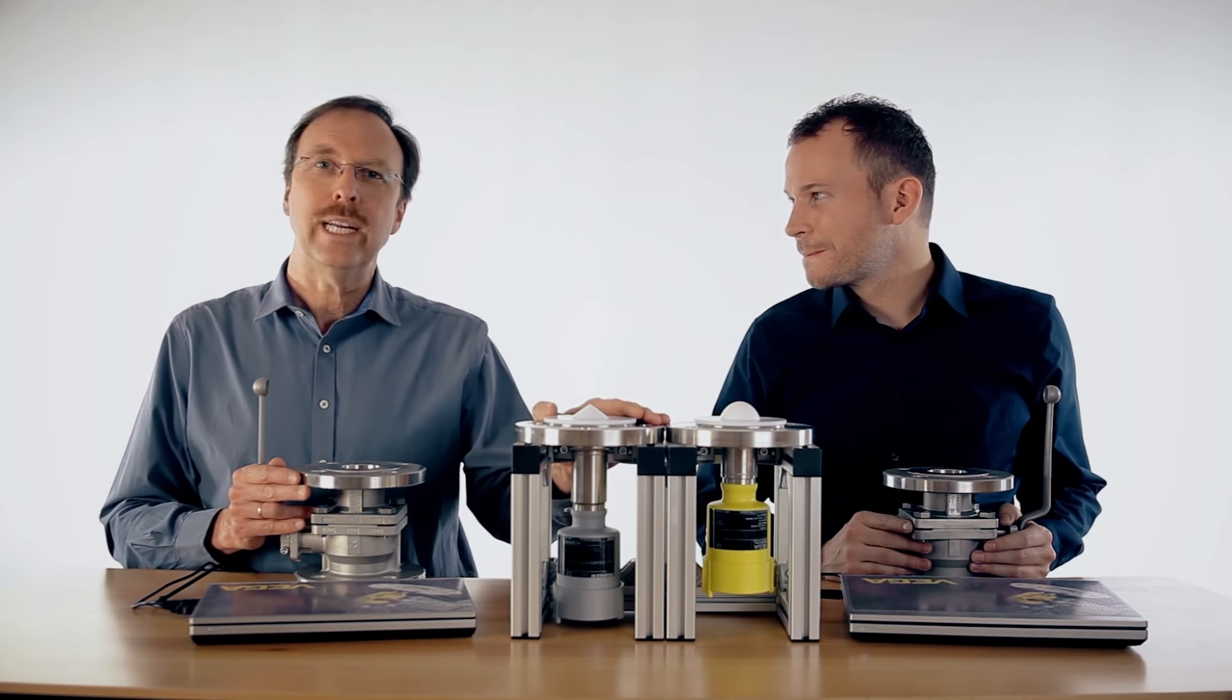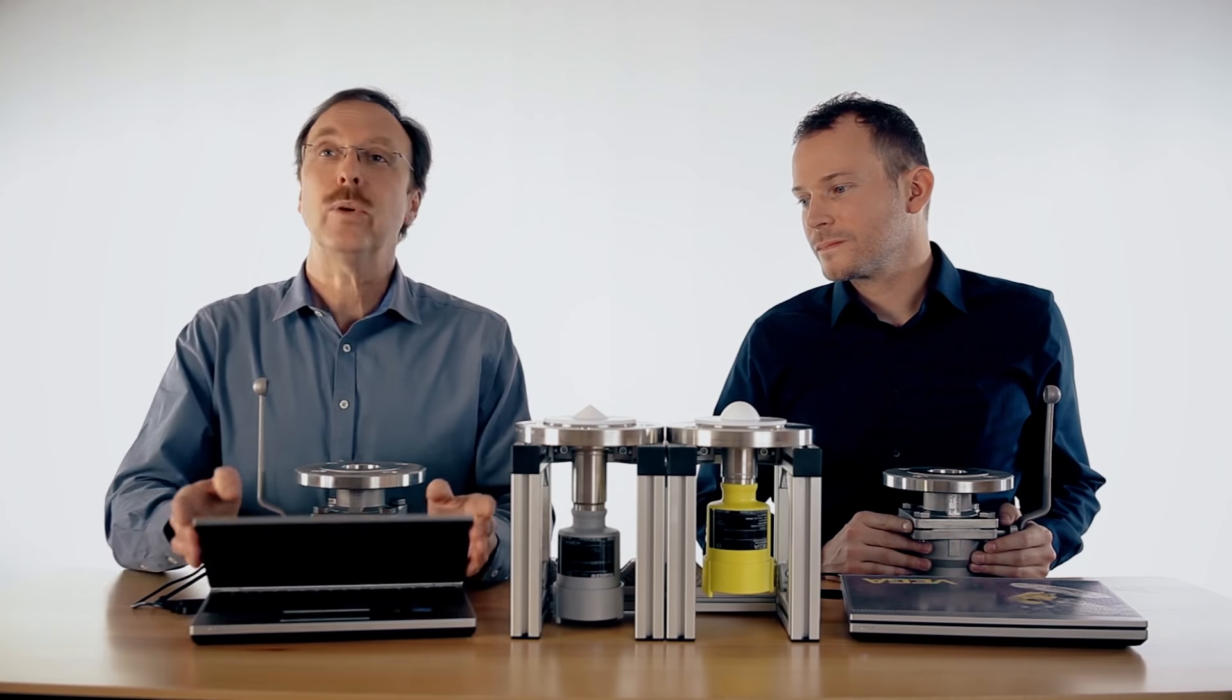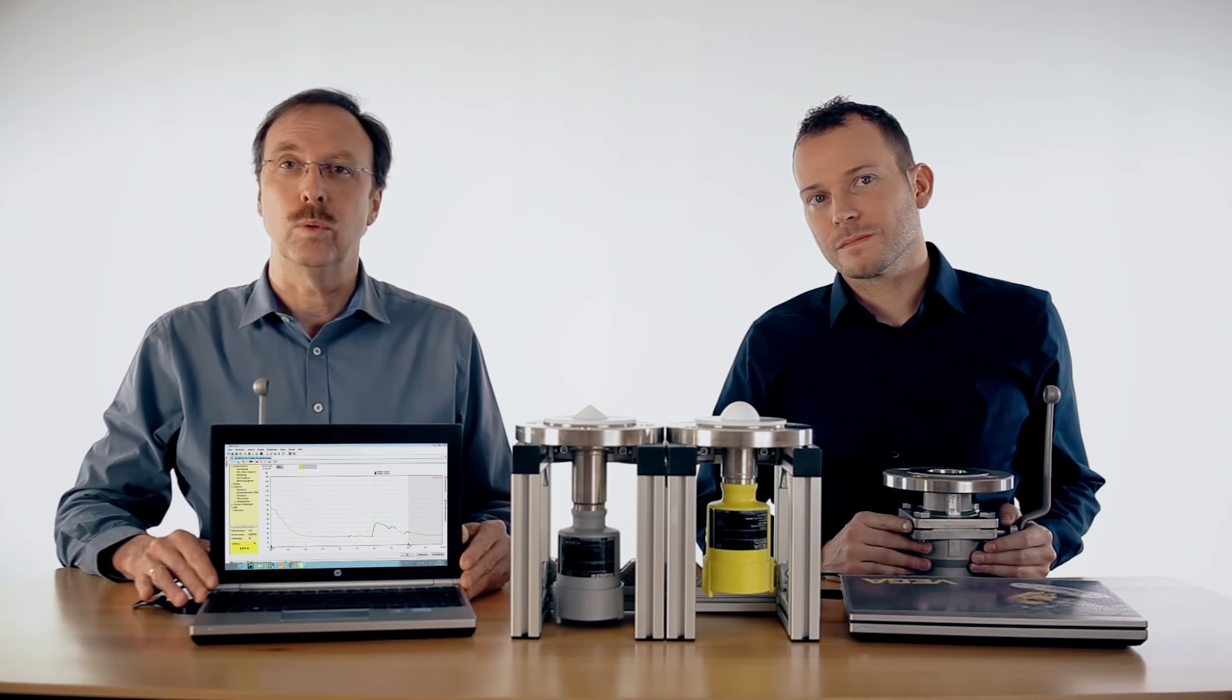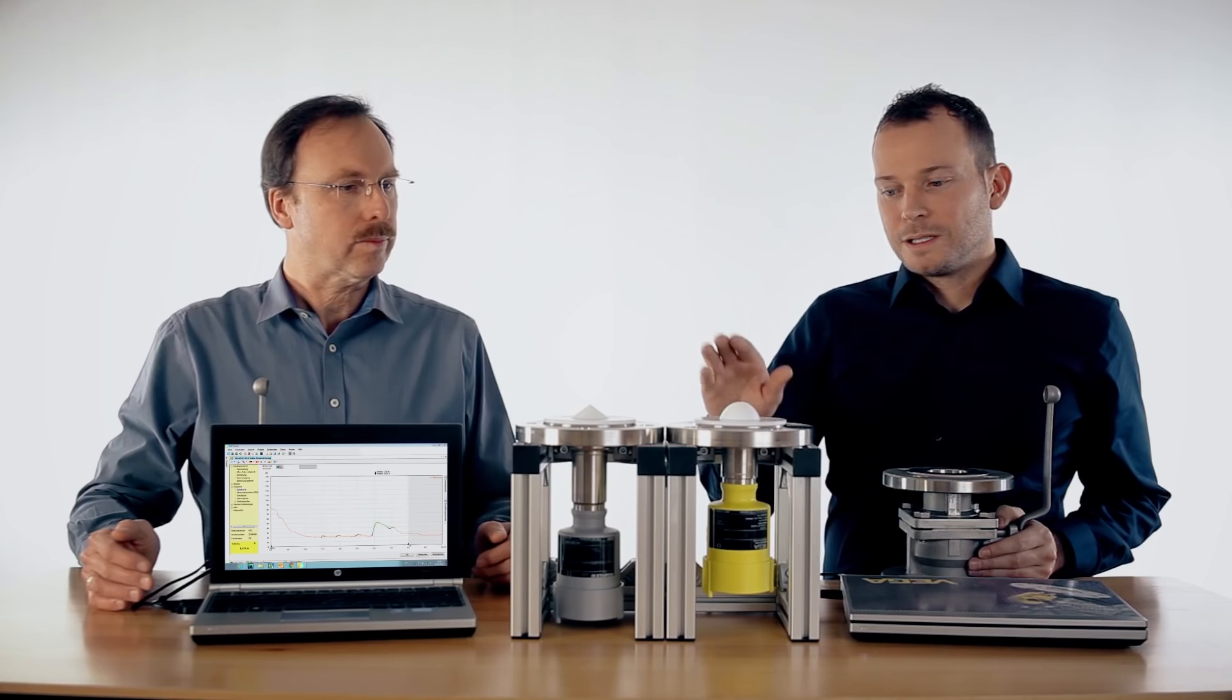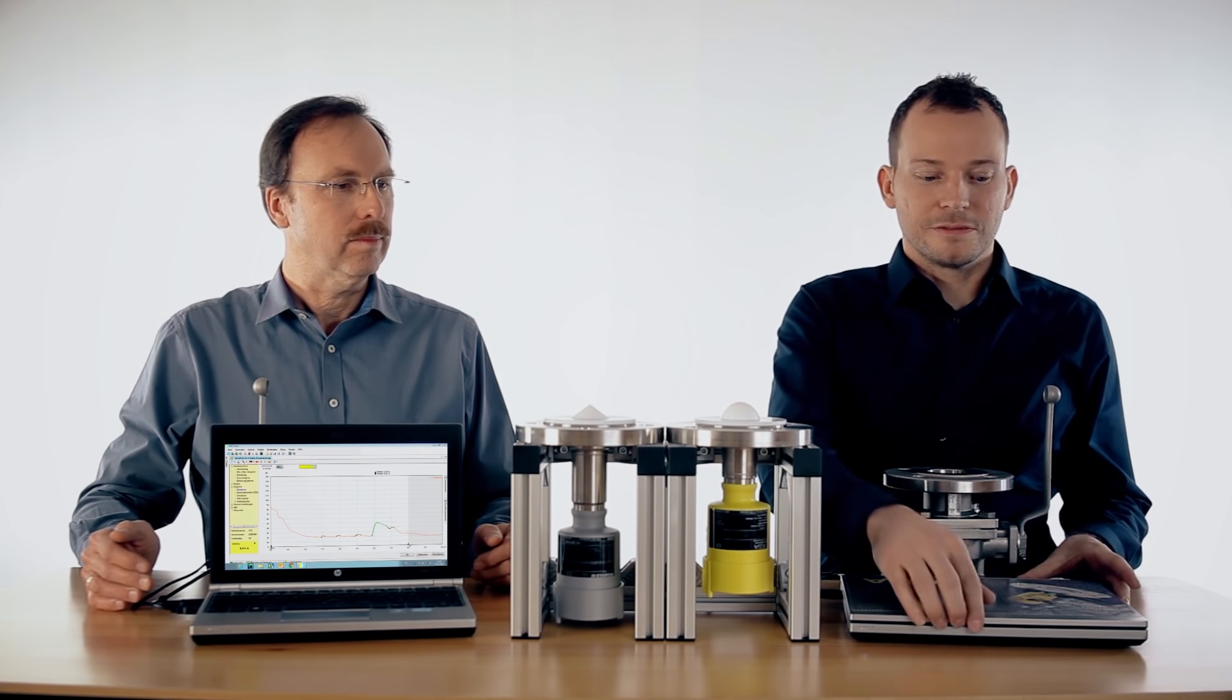We have here a radar sensor with 26 GHz technology and we are measuring at the moment at the top of the roof of this room. You can see a nice echo and there is no influence of any disturbance. The same we have here with the VEGAPULS 64. We are measuring up to the roof and also here we see the echo curve of the sensor.